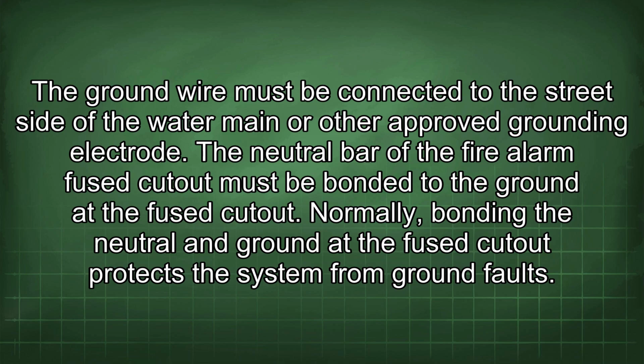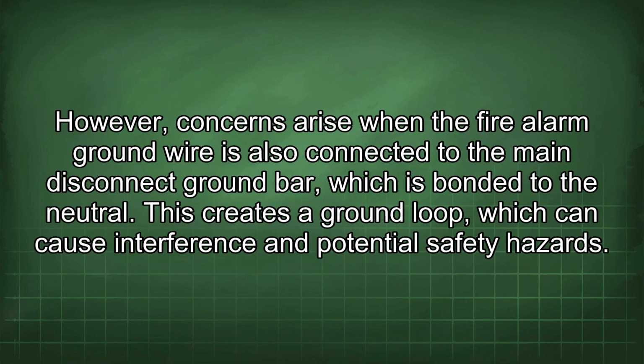The neutral bar of the fire alarm fuse cutout must be bonded to the ground at the fuse cutout. Normally, bonding the neutral and ground at the fuse cutout protects the system from ground faults. However, concerns arise when the fire alarm ground wire is also connected to the main disconnect ground bar, which is bonded to the neutral. This creates a ground loop, which can cause interference and potential safety hazards.